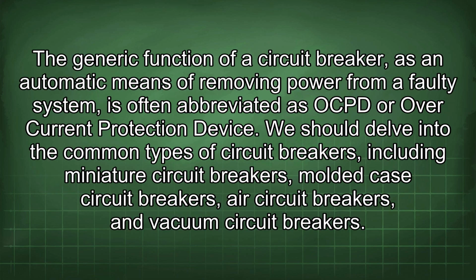The generic function of a circuit breaker, as an automatic means of removing power from a faulty system, is often abbreviated as OCPD or overcurrent protection device. We should delve into the common types of circuit breakers, including miniature circuit breakers, molded case circuit breakers, air circuit breakers, and vacuum circuit breakers.